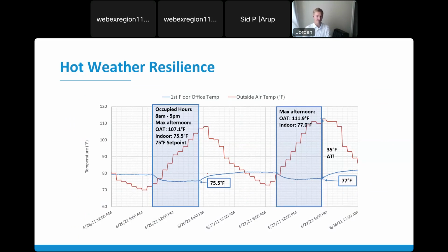We didn't. We shut it off. We wanted to see if we left it on a typical schedule, if it would still be able to catch up, and it was, with that ventilation load being basically eliminated with the heat recovery, 84% sensible heat rejection. That's played a big part of that. It kind of insulates you a little bit from extreme conditions. So there's just a lot of resilience that you bring in when you have this super high efficiency passive heat rejection, or heat recovery in the winter.